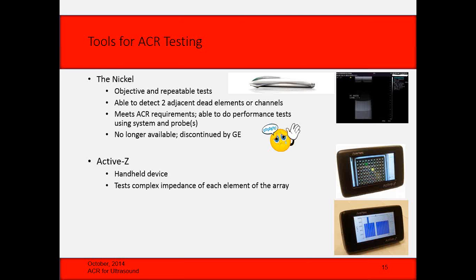So in this case, you see that several of the elements have the same complex impedance, and those are the elements that are good. You notice one that has elevated impedance, so that means that there's probably something wrong with the element, but it could be membrane delamination on the probe. And then you see one that has no impedance, so that would be an indication that the pin is broken. So there's absolutely no impedance, zero impedance. That means that there's no signal getting through, so you've got a broken pin or a broken wire just on the other side of that pin on the connector.